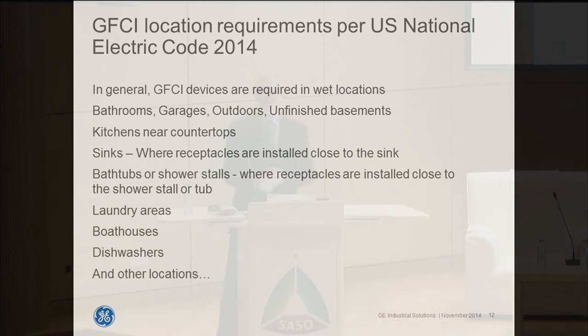Now just talking about areas. I mentioned, as I was talking about deaths from electrocution in one of the early slides, that over time the areas where ground fault circuit interrupters are required have been expanded according to the U.S. National Electric Code. This is kind of a laundry list of areas, but the general areas are wet locations. So clearly kitchens and bathrooms, and then it has expanded to areas where you may have a sink in an area that's not called a kitchen, and so the code has been updated to require that. Laundry rooms, and in addition, an outlet that's close to a shower stall, for example, and other less common areas like boathouses. These are also required for automatic dishwashers and areas like that.